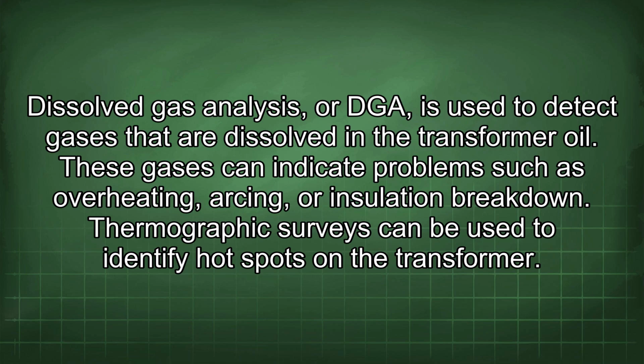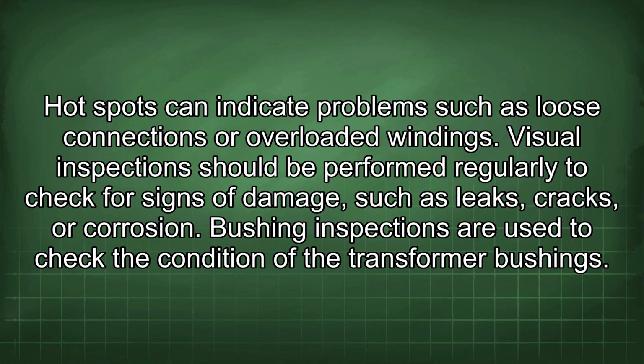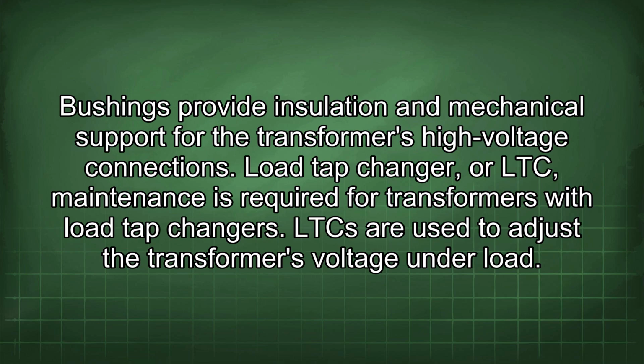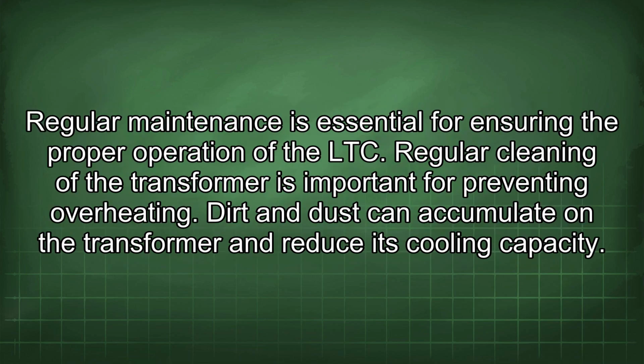Thermographic surveys can be used to identify hot spots on the transformer. Hot spots can indicate problems such as loose connections or overloaded windings. Visual inspection should be performed regularly to check for signs of damage, such as leaks, cracks, or corrosion. Bushing inspections are used to check the condition of the transformer bushings. Bushings provide insulation and mechanical support for the transformer's high-voltage connections. Load tap changer, or LTC, maintenance is required for transformers with load tap changers. LTCs are used to adjust the transformer's voltage under load. Regular maintenance is essential for ensuring the proper operation of the LTC.